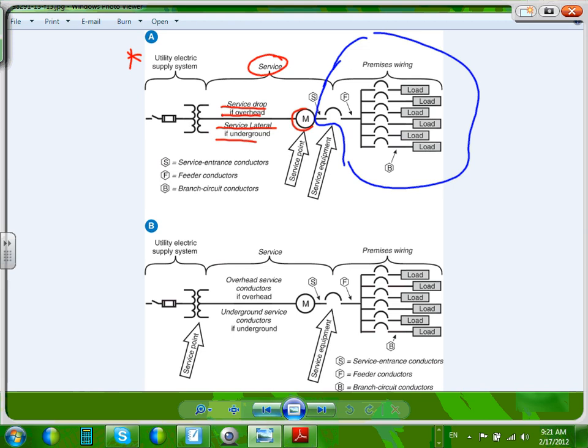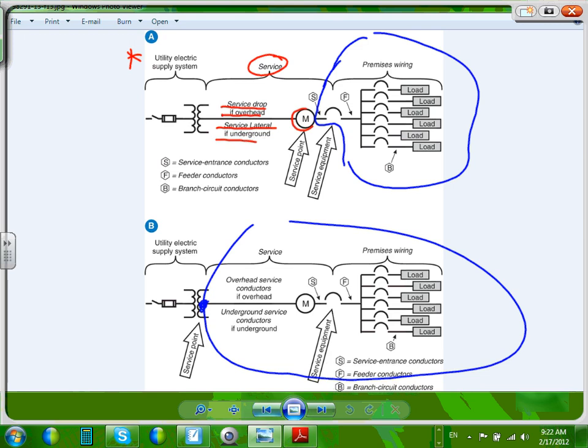That's probably 90% of the time, guys. You're going to come to the meter cabinet, from the meter cabinet into your building. That's called the service point. If you put your service point right here, can you guys see where you put your service point right in here, right? Then everything here is owned and operated by you.